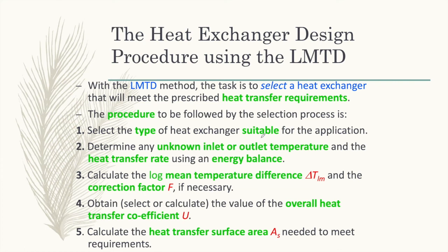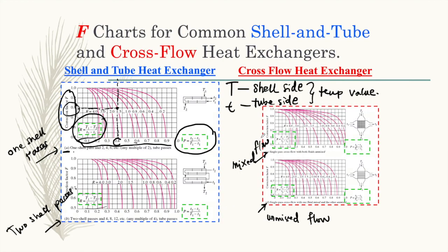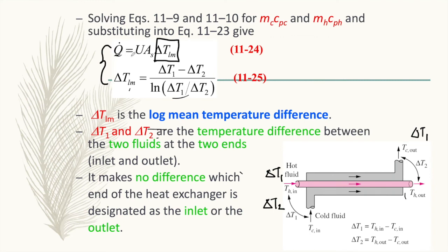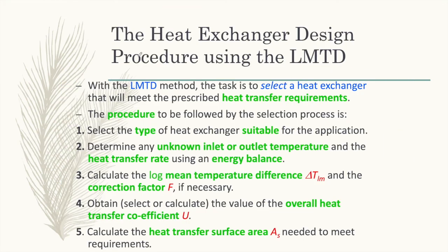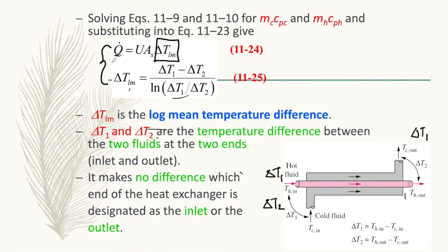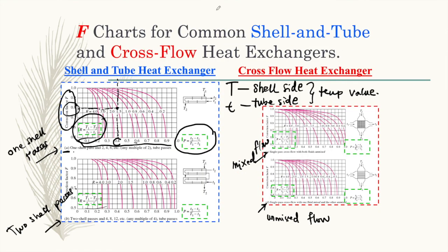Fourth, obtain the overall heat transfer coefficient U using a suitable method or equation. Fifth, calculate the heat transfer surface area A_s. Finally, substitute all values into the equation Q-dot equals U·A_s·F·delta_T_lm to determine the rate of heat transfer. Remember that for shell-and-tube or cross flow heat exchangers, you must include the correction factor F obtained from the chart.